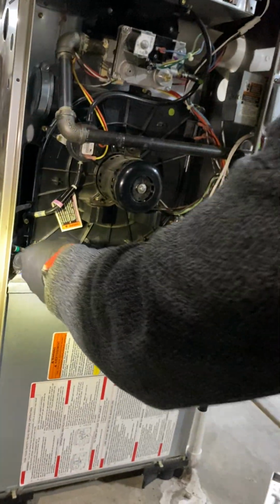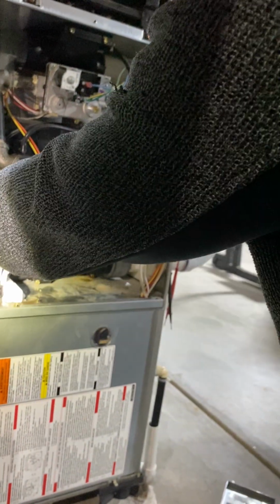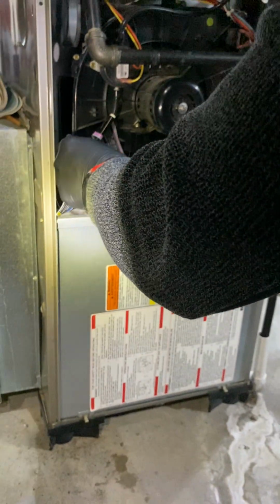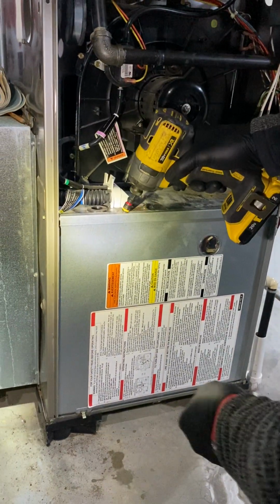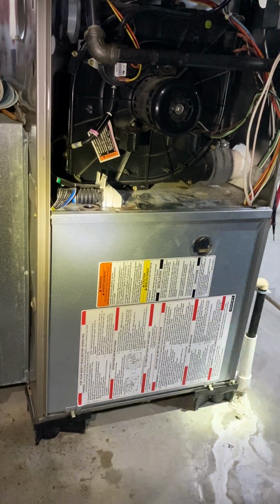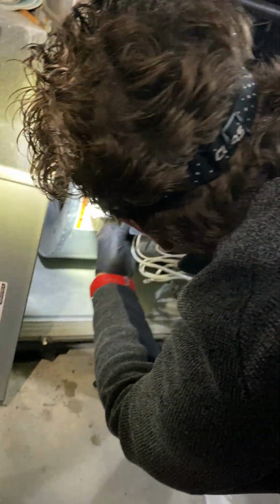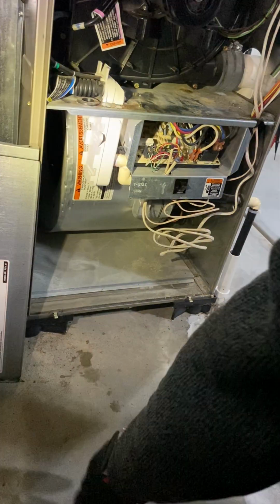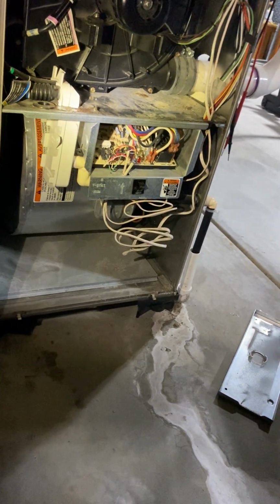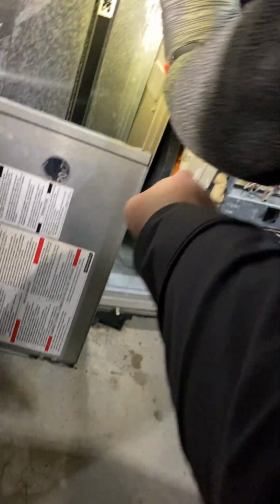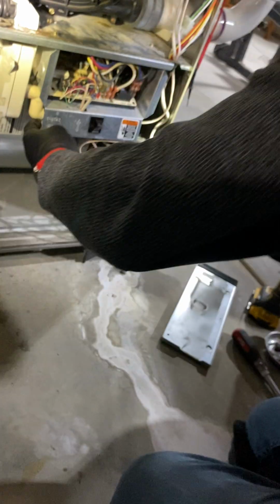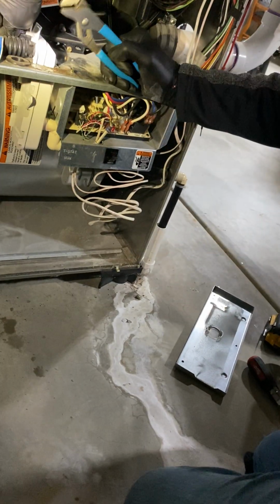So that's what this trap is for. If water is not going through here, water gets stuck in the inducer motor or in the heat exchanger part, and then it fills up, and water will come through this tubing and disrupt the pressure switch. So this P-trap, as you realize, all P-traps are different. They're all installed differently. This P-trap comes underneath, down through here, goes through here, and then out through here. You can tell this hasn't been cleaned when you can't even get the tubings off.